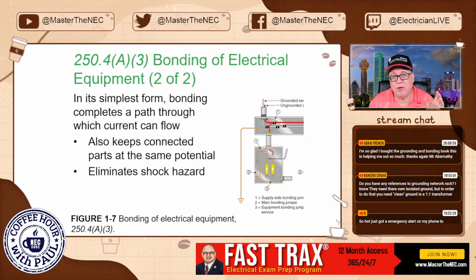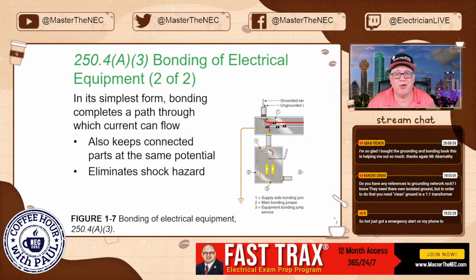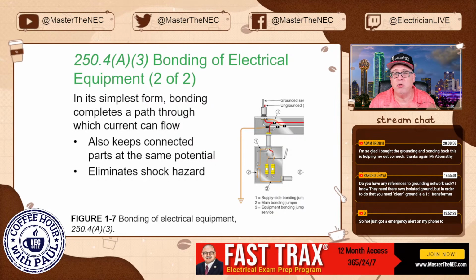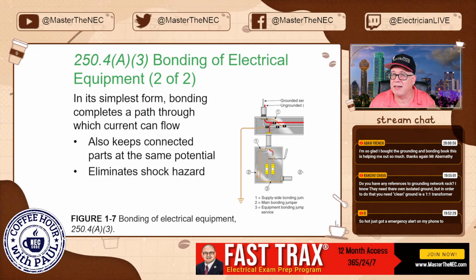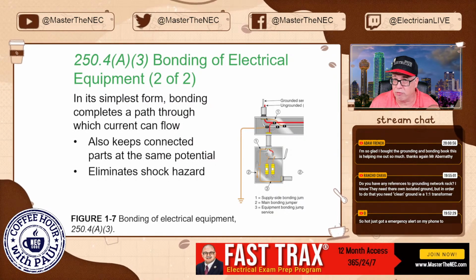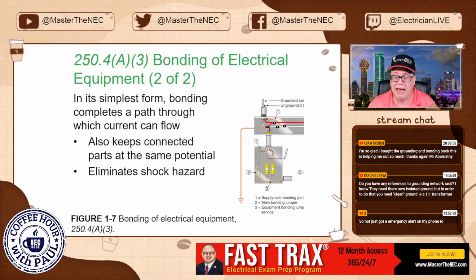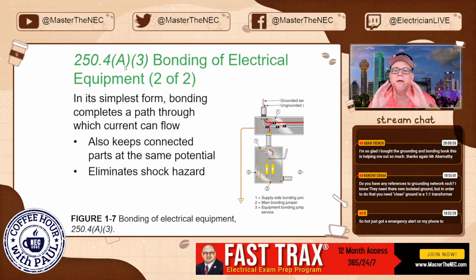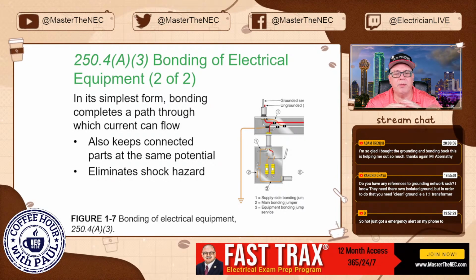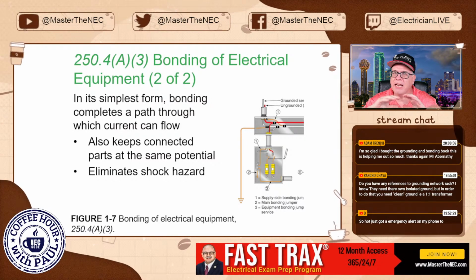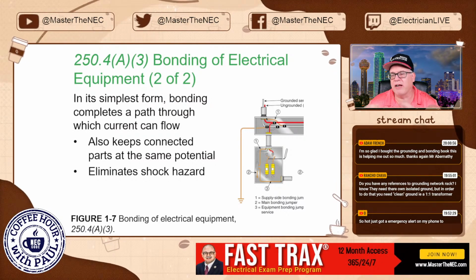But as many people will tell you, a lot of times those service drops and things like that are just fuses, because we all know the utility doesn't require theirs to be as large as what we would run, right? We all know that. So the real issue here is putting everything at the same potential, and it helps reduce the shock hazard as a result of that.